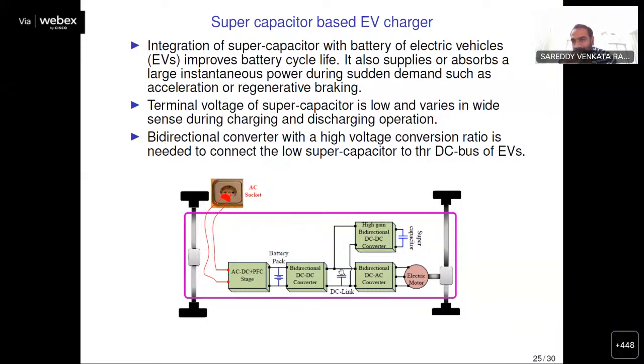I didn't get that point. It's not exactly a disadvantage, but the voltage output of the supercapacitor is very low. The current will be high, but the voltage is low, around 24 volts. The DC link voltage will be very high, around 300 volts. So you want to step up this 24 volts to 300 volts, almost a 10 times gain.